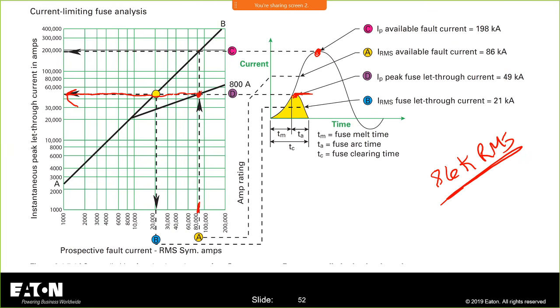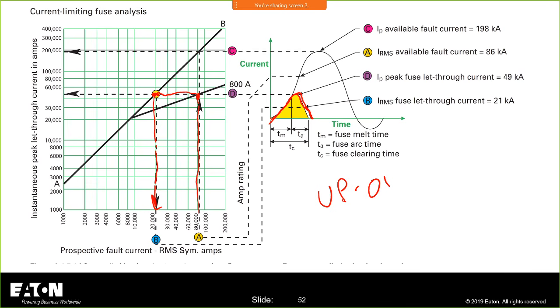Now, if I want to know what my new RMS current is, this new waveform, I know that I'm going to clear in less than a quarter cycle. I want to know what my new RMS value is. I go up, I hit that line, I go over to the AB line, and I come down. That is called the up, over, down method. And what that tells me is what the RMS value is of this new waveform, because my equipment won't see this whole short circuit current. It's only going to see this little blip of current.